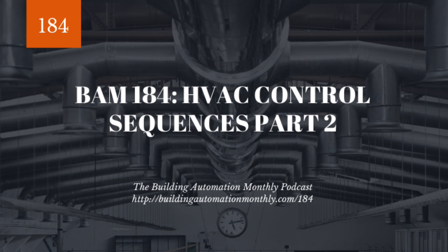And those set points are typically controlling the zone temp, but sometimes controlling to supply or discharge air, depending on what you want to call it. Personally, I like to call everything discharge air if it's being discharged. And I like supply air to be the incoming air, especially at VAV boxes from an air handler. It's more clear that way. Supply air is being supplied to a unit. Discharge air is being discharged from a unit. That's how I like to word things. That makes sense to me.